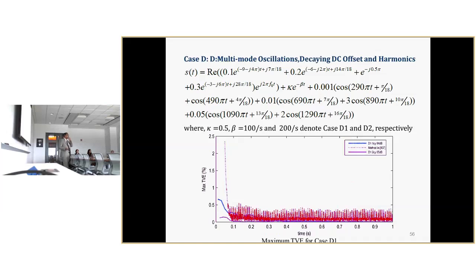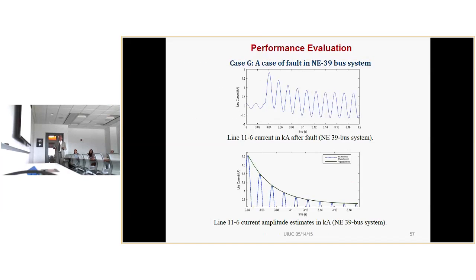So is there additional computational cost associated with this method compared to the existing method? No, we actually verified it is well within one cycle; it is much less than one cycle for the value calculation. 20 milliseconds is one cycle. It was about 2 or 3 milliseconds. How long does it take to compute the phasor with the conventional method? Adaptive DFT? Adaptive DFT also is fast, but accuracy is less. In certain cases, it crosses the TVE requirement. But is it much faster than the method you propose? No, not faster, but more accurate. It is almost the same time, but more accurate. Okay. And this shows the tracking of the actual waveform.